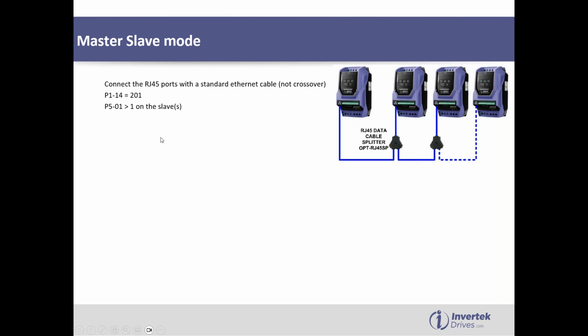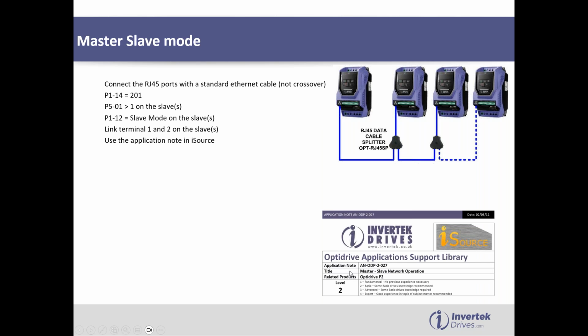All we do is open up the extended menus on the drives, and on the slaves, the address, so the drive address, P501, just has to be greater than 1 on the slaves. And then you tell the slave drives with the control mode that they're in slave mode. And all you have to do is enable the drives, and then they will follow exactly what the master tells them to do. Again, we have an application note available to help you set that up very easily, very quickly.